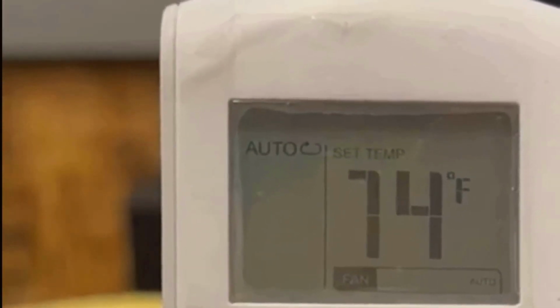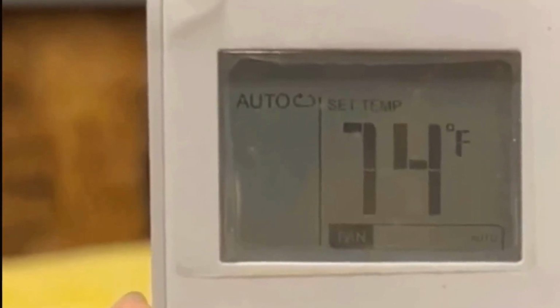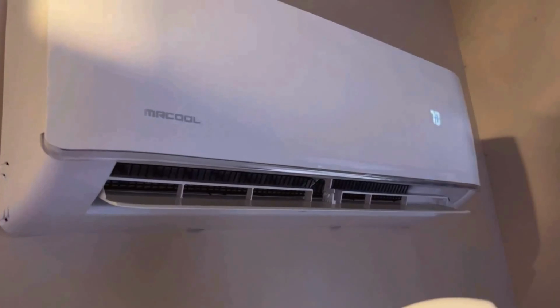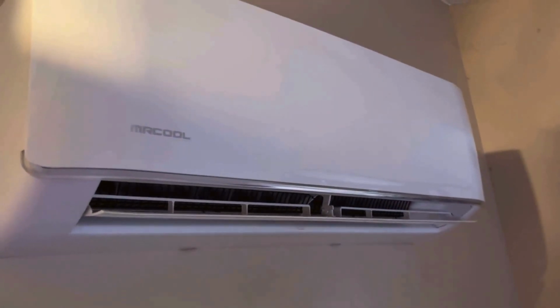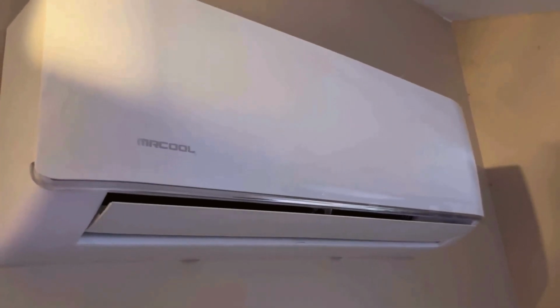Installation details that helped me as a non-pro. I used a proper 3.5-inch hole saw for a clean sleeve through the wall, sealed the sleeve edges inside and out with foam and exterior-grade sealant, and mounted the indoor unit so the filter door clears the ceiling for maintenance. I registered the warranty immediately and kept photos of the serial numbers in my install. This model lists 5-year parts and 7-year compressor coverage.